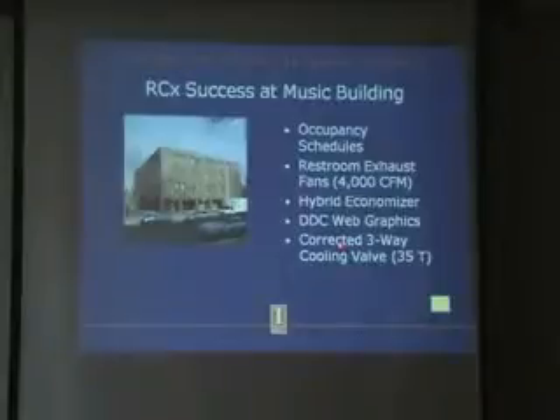One of the smaller festering things we found was a three-way valve on the chilled water system. A three-way valve means the chilled water either goes through the coil or gets bypassed and goes back to the Avid power plant. We were scratching our heads, wondering why we had 35 tons of load here in the dead of winter with no cooling in the building. When they put the chilled water loop in, they had changed out most of the chilled water valves in the building, but one was missed.